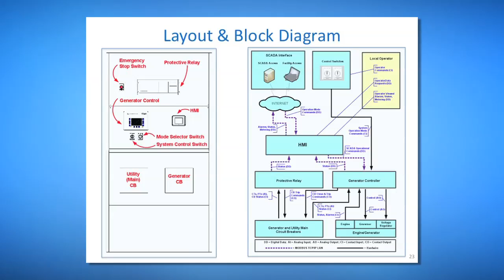If we look at the block diagram on the right, you can see how the information flows. From the bottom are the field assets, the circuit breakers and generators. That goes into protective relays and generator controls, which are kept separate because that's good philosophy, control and protection are separated. Then there's the HMI, which acts as the buffer to the internet. We use a lot of GE equipment for the HMI and some PLC control, and then we use mostly public IP to transmit the information, whether to start or run, and for maintenance.